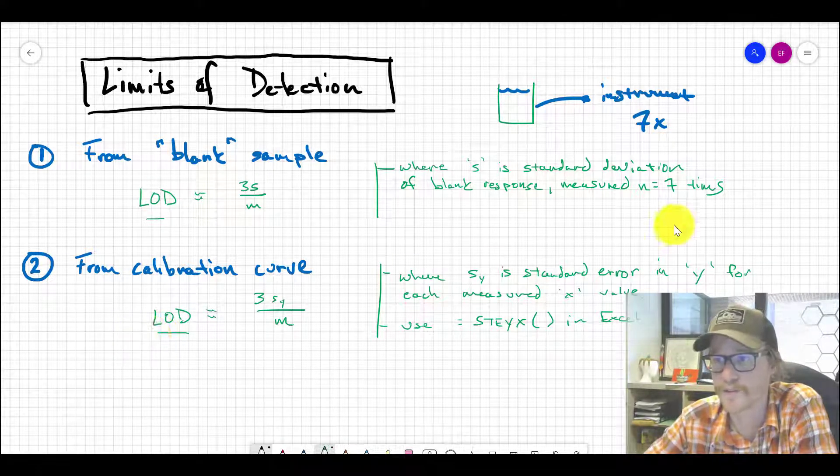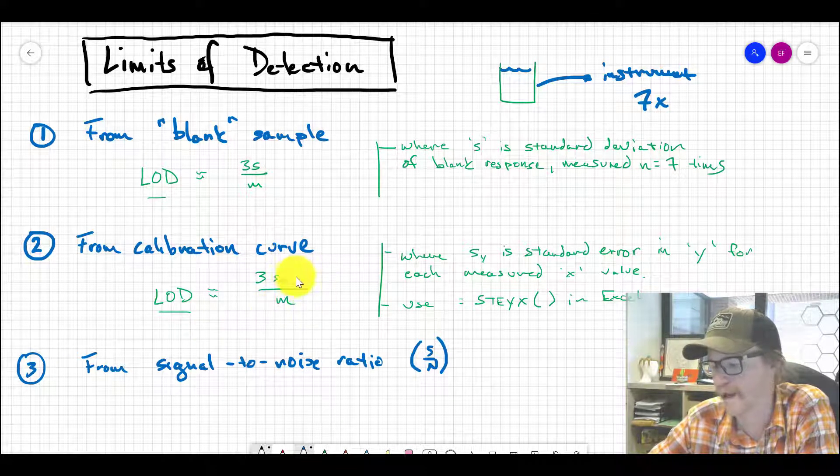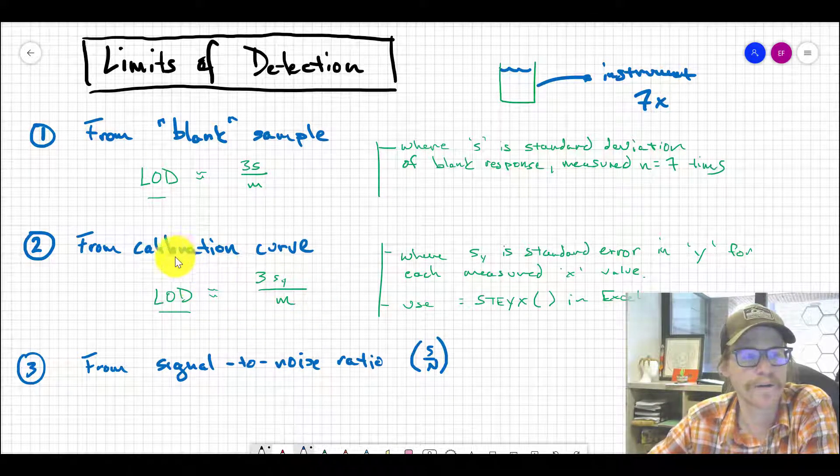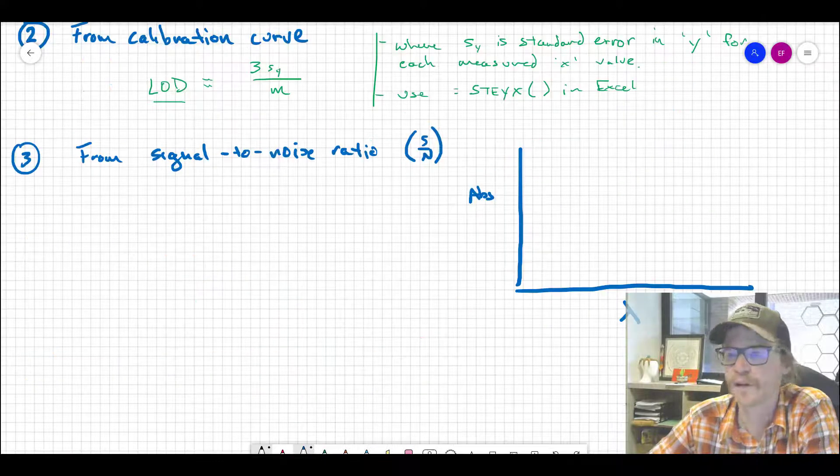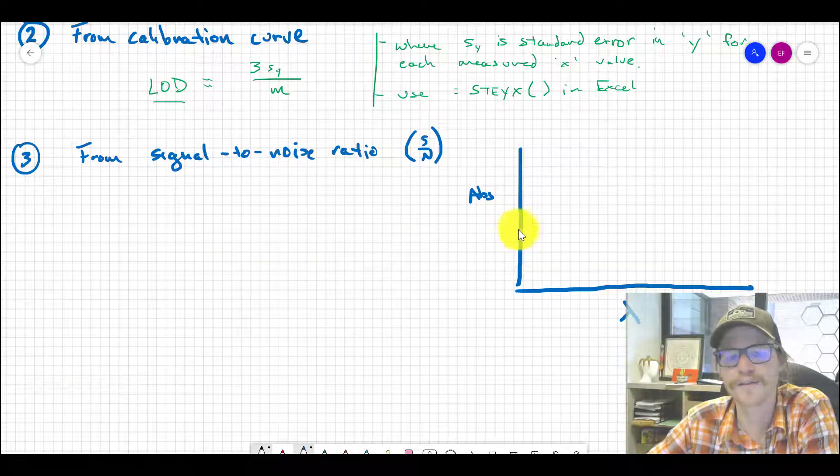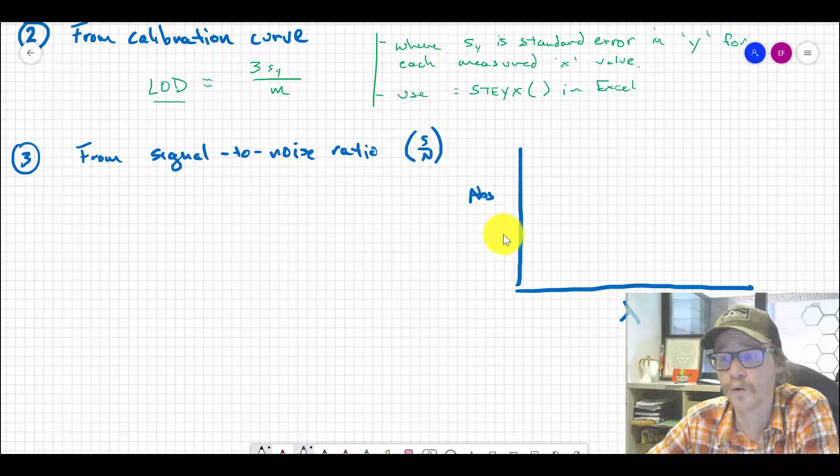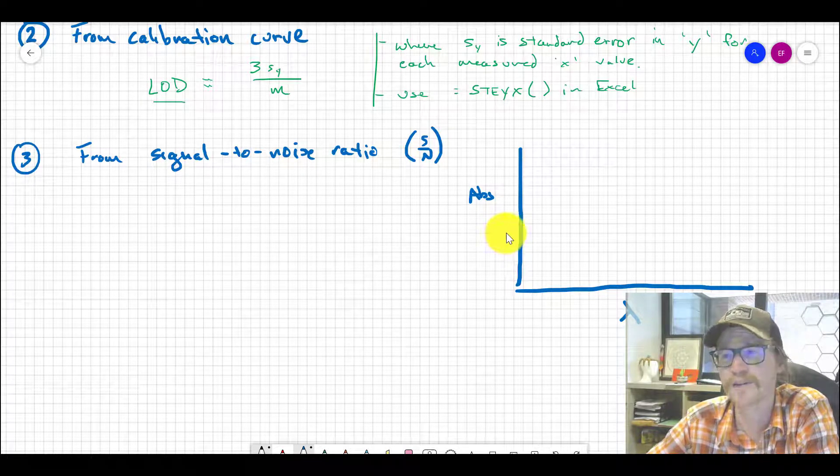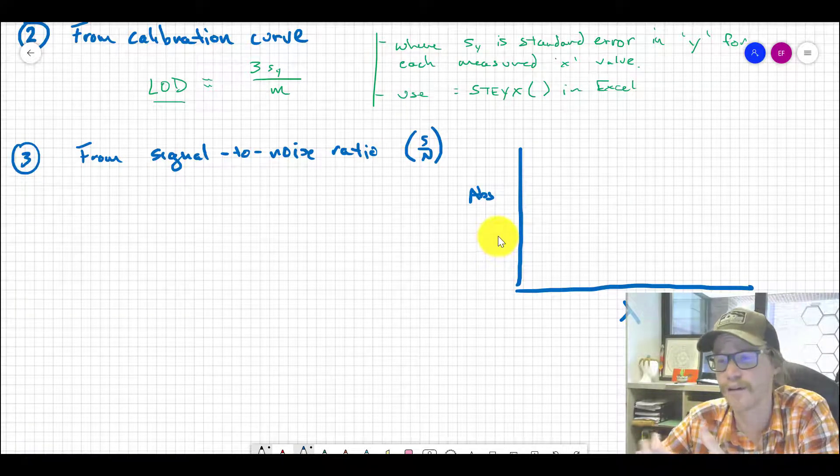The third method is what I'd consider a quick and dirty method. You can estimate the limit of detection from the signal-to-noise ratio. The signal-to-noise ratio is the relationship between the response from the analyte versus the response from the instrument background itself—usually electronic or thermal noise.